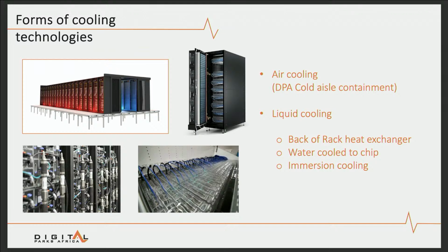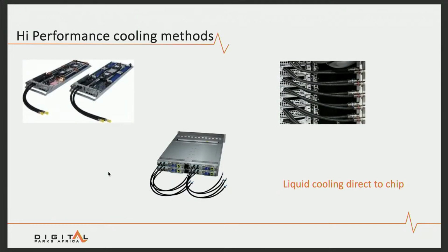So additional forms of liquid cooling that we've seen is really the direct-to-chip cooling, where water is directed to a heat transfer plate that is mounted above the chip on the server chassis. And then we also have immersion-based cooling. So I'll show you a couple of samples of that. First of all, the liquid cooling direct-to-chip. There you see it on a sub-assembly.